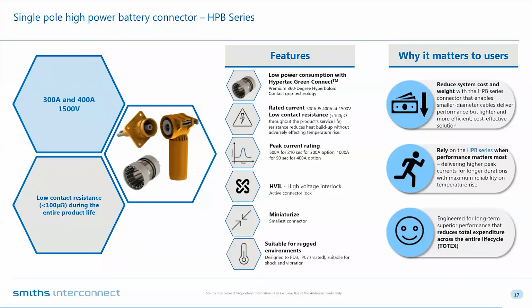Then Giacomo showed you the results on peak current. The product has been designed for applications that require peak current—not just as an intermittent surge, but for applications where peak current is part of the duty cycle. As a result, the product is capable of sustaining peak current for not just tens of seconds, but 210 seconds at 500 amps, and up to 90 seconds at 1000 amps. The product has been designed for sustaining high current without thermal derating or reliability concerns.